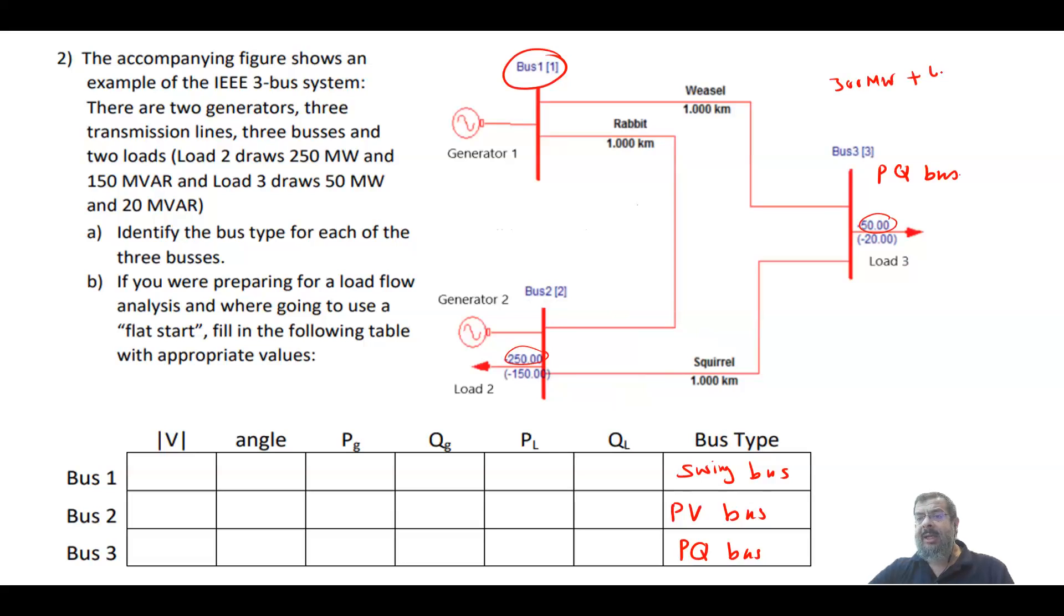Your generator has to supply this. Now you don't know the losses before you solve the system, so you cannot assign the exact number of power at the beginning. We keep a bus we call the swing bus or the slack bus, and whatever is left of the power can be assigned to that bus. These are the three different buses you have in the power system for load flow analysis.